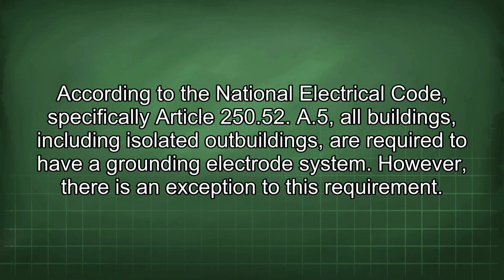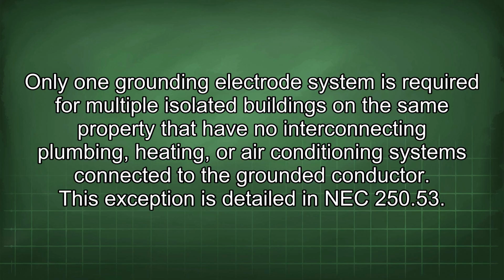According to the National Electrical Code, specifically Article 250.52(A)(5), all buildings, including isolated outbuildings, are required to have a grounding electrode system. However, there is an exception to this requirement. Only one grounding electrode system is required for multiple isolated buildings on the same property that have no interconnecting plumbing, heating, or air conditioning systems connected to the grounded conductor. This exception is detailed in NEC 250.53.